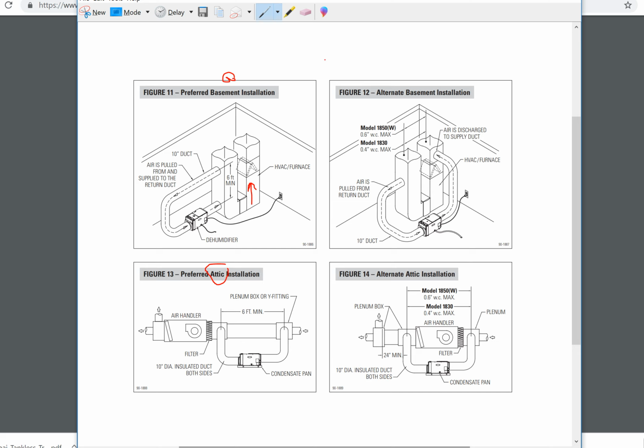On the left side is the preferred installation, which is what we call return to return. On the right side, these alternatives are for return to supply. And so all four are acceptable. Really, it's two styles, return to return or return to supply. Both are acceptable. But what's preferred? Well, return to return is preferred, and for a couple of different reasons.